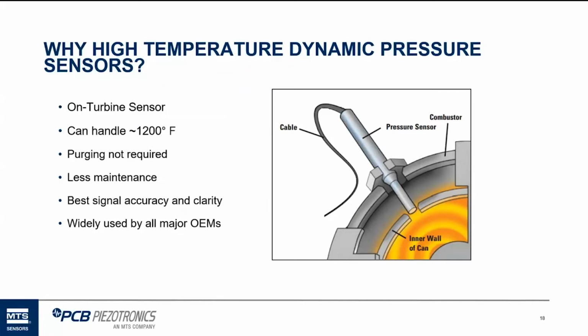So again, part of that is maintenance. If those tubes get plugged, it requires a lot of maintenance to keep those clean. Sometimes they've got to replace a tube, especially an infinite tube system, if it gets too plugged up, and it's really expensive to replace those. Nowadays, I think all OEMs are using high temperature dynamic pressure sensors on the turbine. I don't think anybody's going the other routes anymore that I can think of.